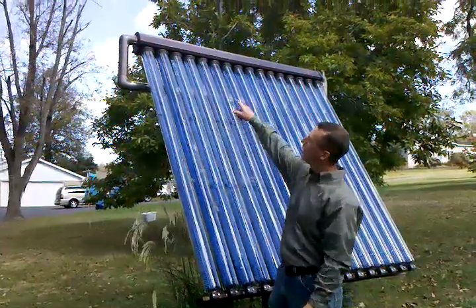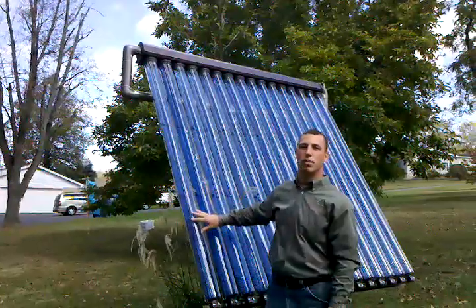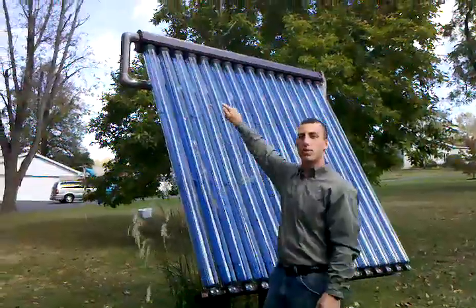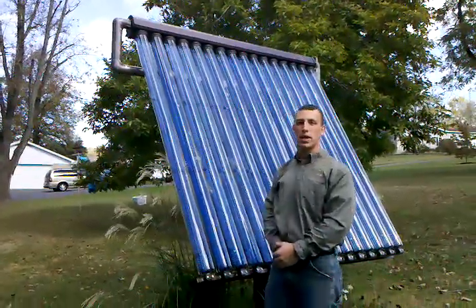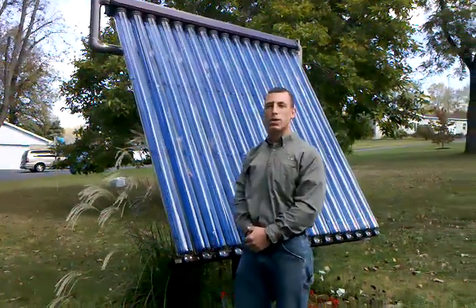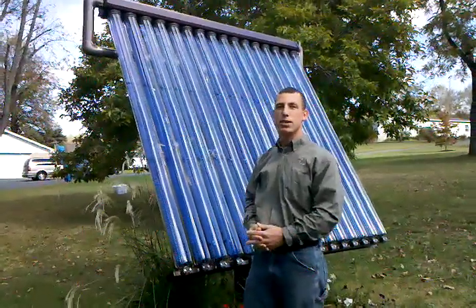Up there is the header on the top, and that's where the heat energy is transferred from the tube — the heat pipe technology — into the header. We have a water-glycol solution that flows across the header and carries that heat energy into your domestic hot water tank. That's basically how evacuated tube technology works. This is a single wall vacuum, which means that your collector surface is inside the vacuum itself.